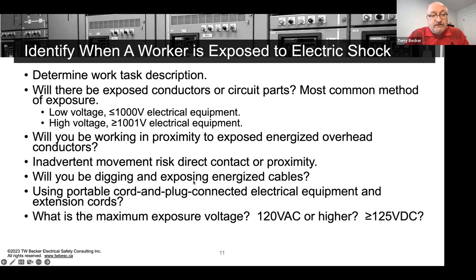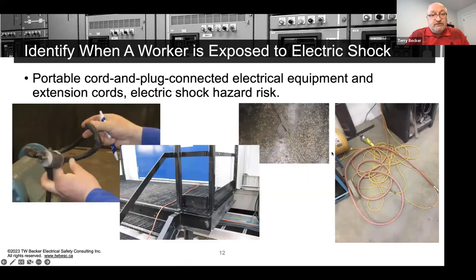Digging, so exposing energized cables. And lastly, we cannot neglect using portable cord and plug connected electrical equipment and extension cords. And the worker needs to understand the maximum volts of exposure. And it really starts with nominal 120 volt AC single phase. And for DC, and again, DC is still sort of evolving for electric shock and arc flash, but it's greater than or equal to 125 volts DC, UPS battery output or significant DC power source.